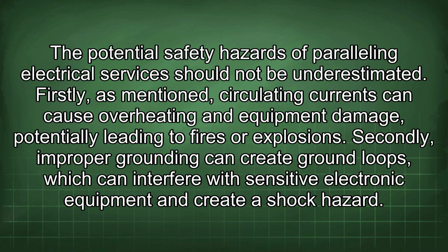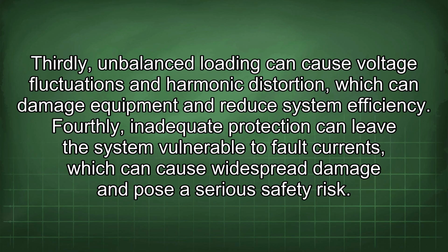The potential safety hazards of paralleling electrical services should not be underestimated. Firstly, as mentioned, circulating currents can cause overheating and equipment damage, potentially leading to fires or explosions. Secondly, improper grounding can create ground loops, which can interfere with sensitive electronic equipment and create a shock hazard. Thirdly, unbalanced loading can cause voltage fluctuations and harmonic distortion, which can damage equipment and reduce system efficiency.